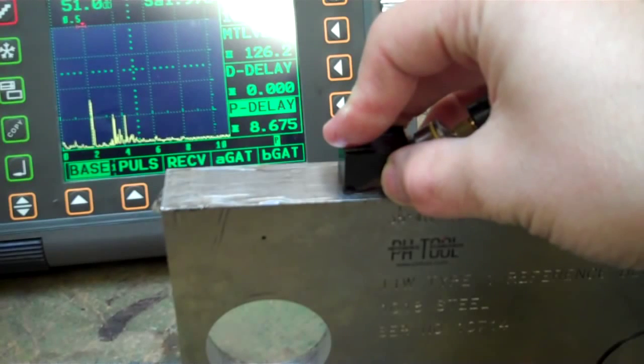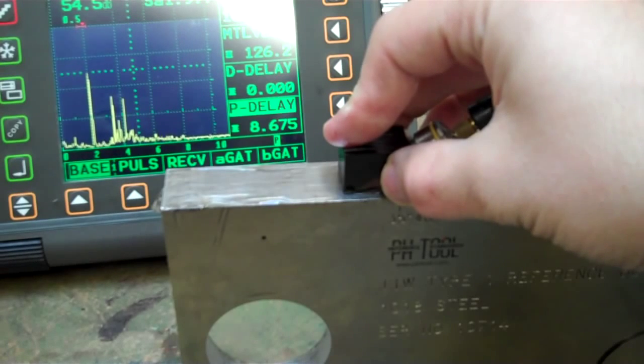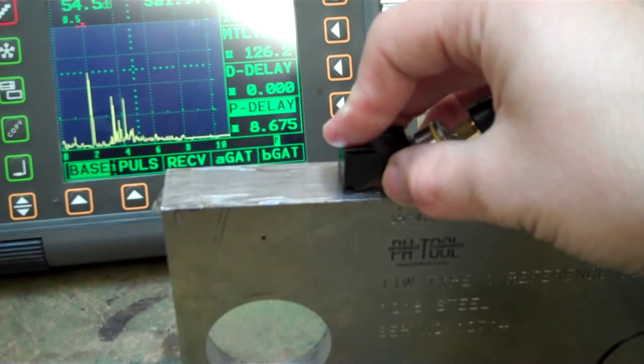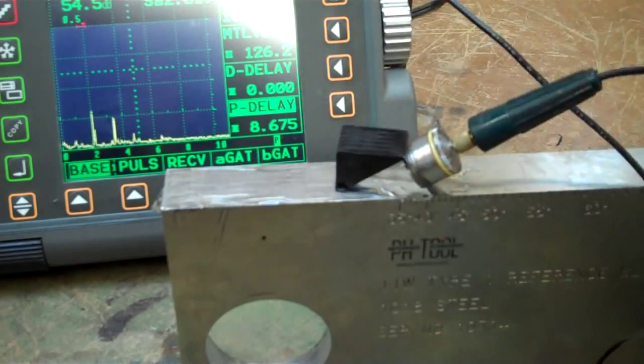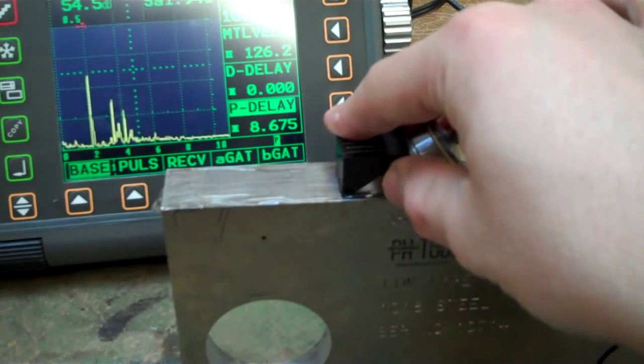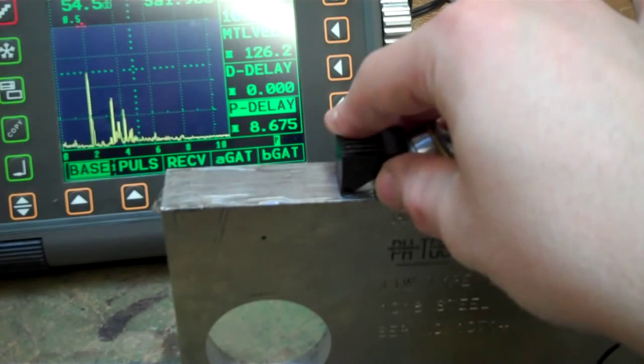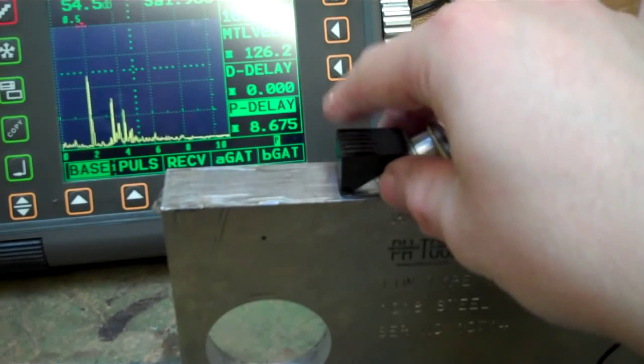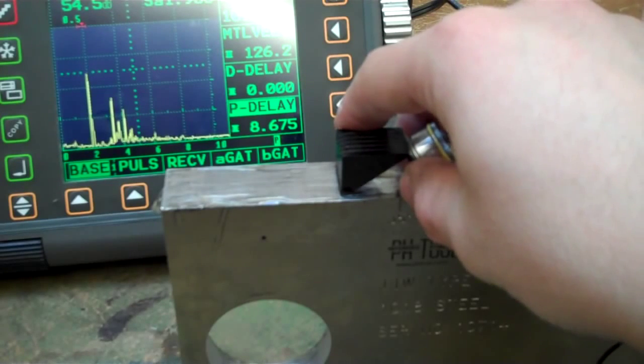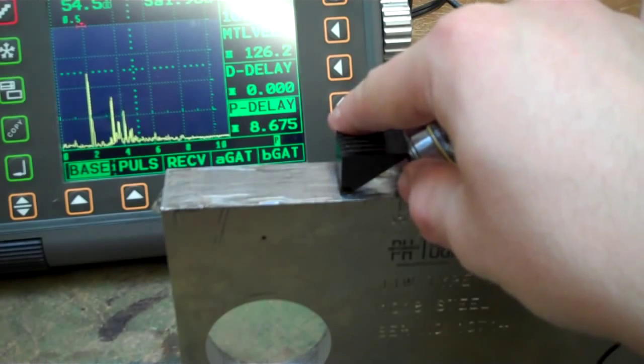And now to set that sensitivity, I'm going to run my gain up to where the signal is at 50% screen height. So once it is at 50% screen height, I have set my sensitivity. Okay, and the next part of that tells me that I need to add 8 dB and scan a weld plate. So we'll scan the weld plate in the next section. Okay? Anyway, using that, now we have calibrated to D1.1 on an IIW block for ultrasonics using shear wave.